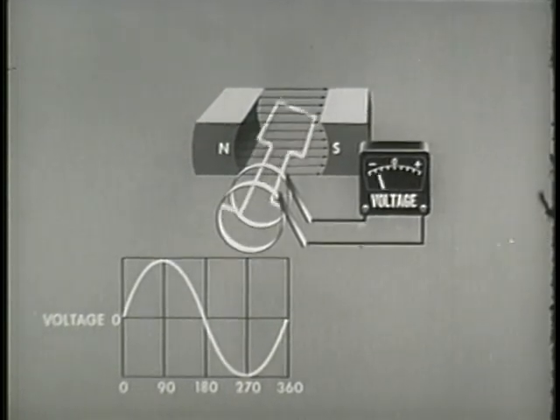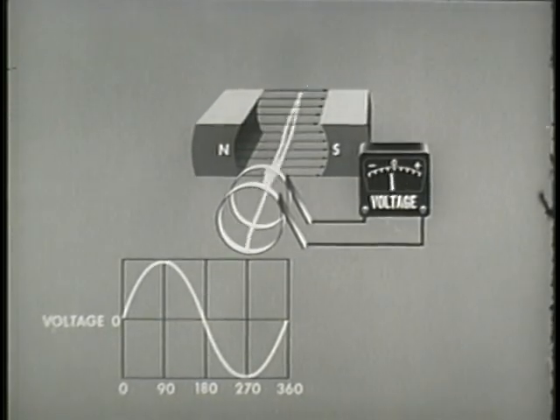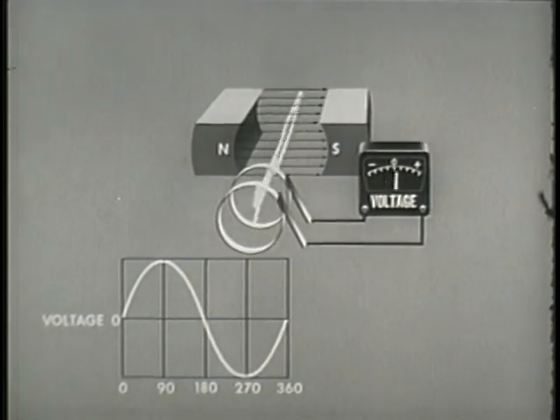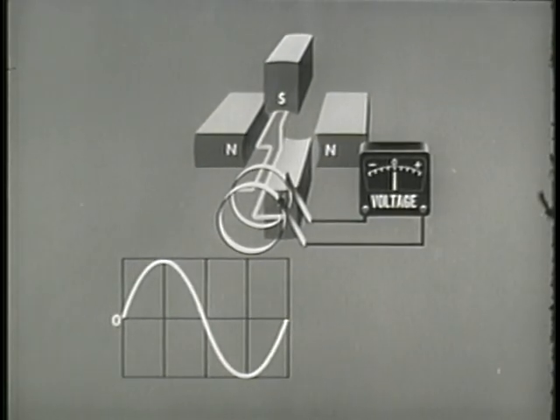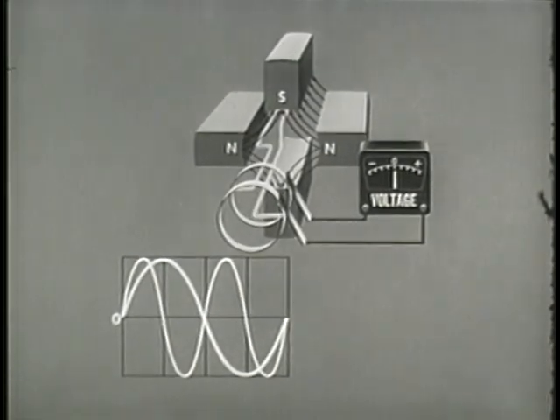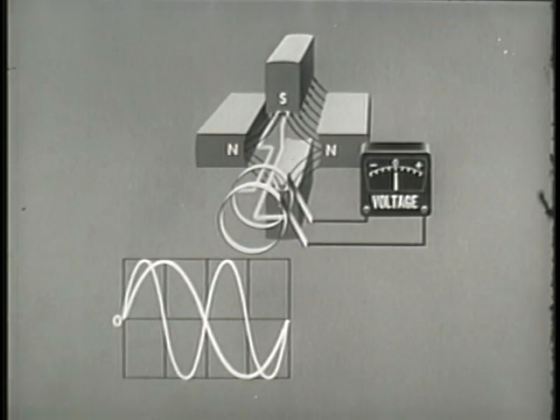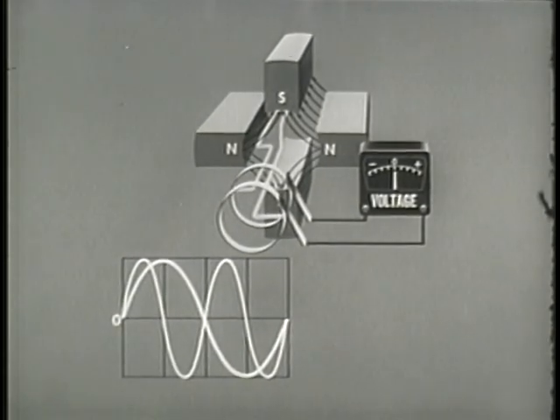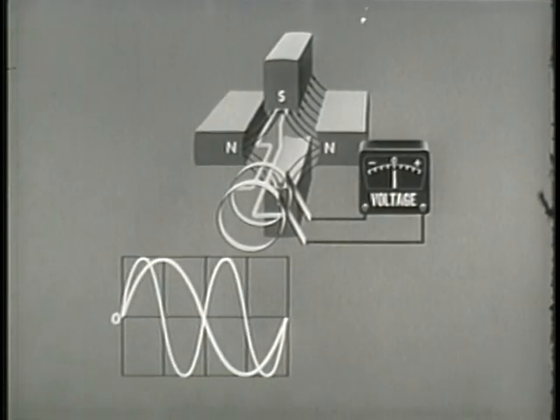In this example, the two-pole machine used has one magnetic field. As the armature makes one revolution, one magnetic field is traversed. Adding another pair of poles adds another magnetic field — now there are two magnetic fields. The armature moves through one field in half a revolution. In one complete revolution of 360 mechanical degrees, the armature passes through two fields equal to 720 electrical degrees, and two cycles of AC are generated.